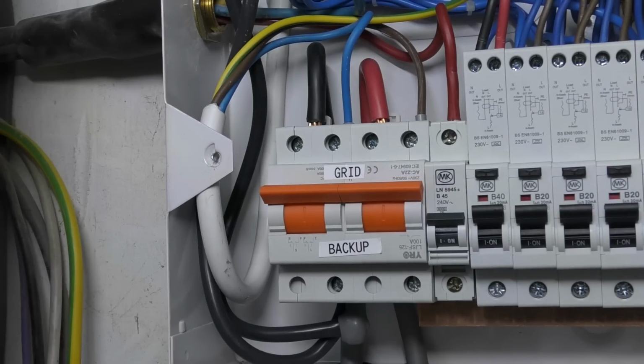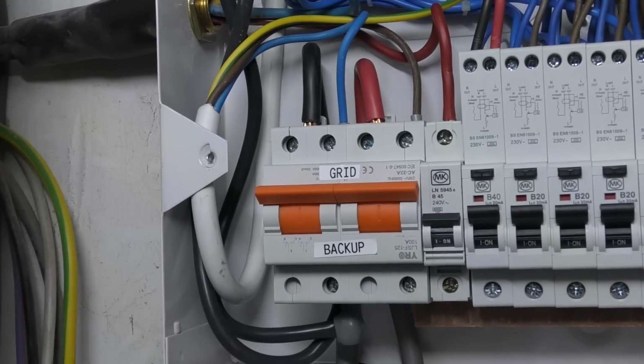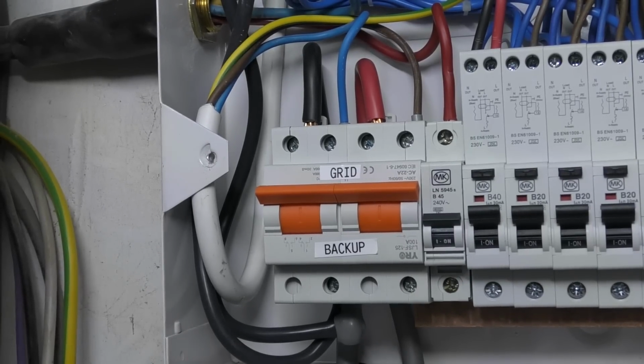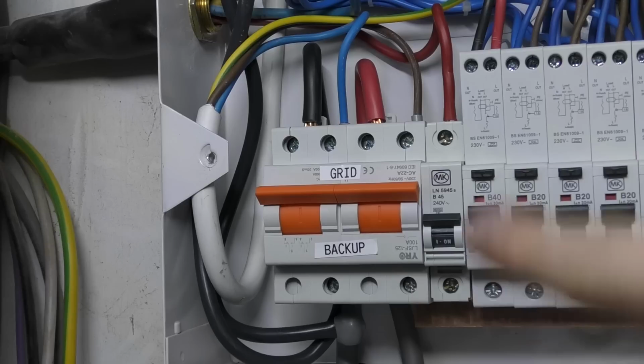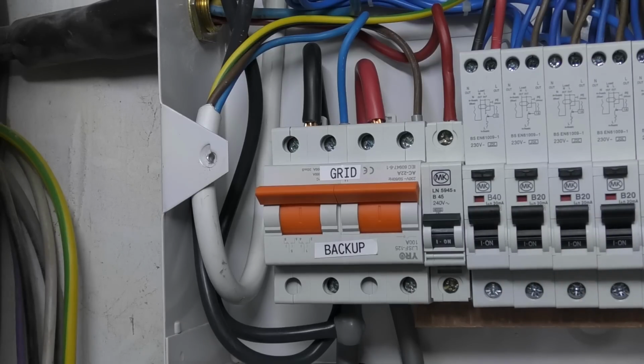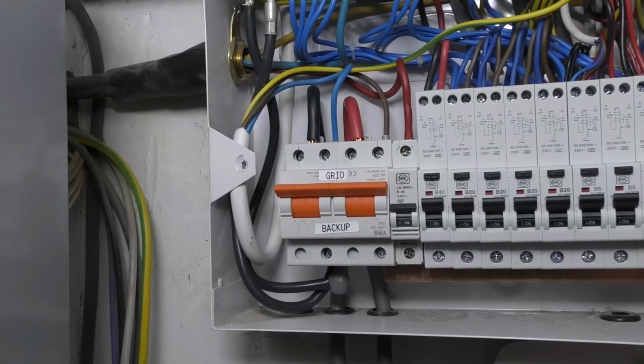The other thing I like about this one, it's similar to that dual breaker in that it does have a centre off position. That UK 125 amp unit I found doesn't have a centre off, so it's literally A or B, and there's no way of having a centre isolated position. So to switch over, this has got a 100 amp rating, but it's not a good idea to switch these things with a load.